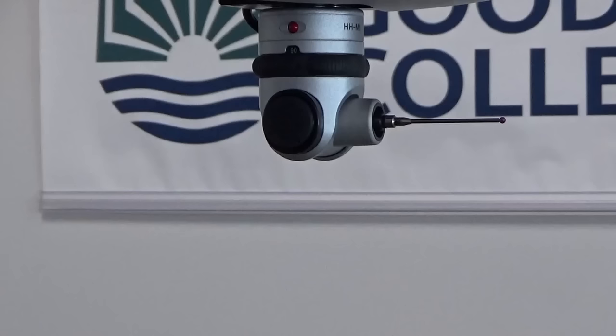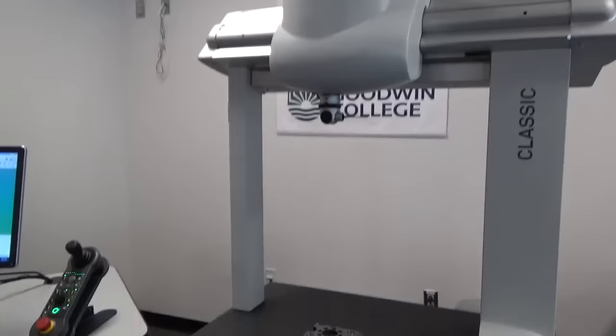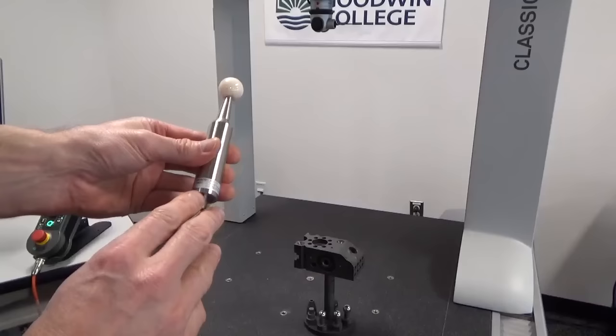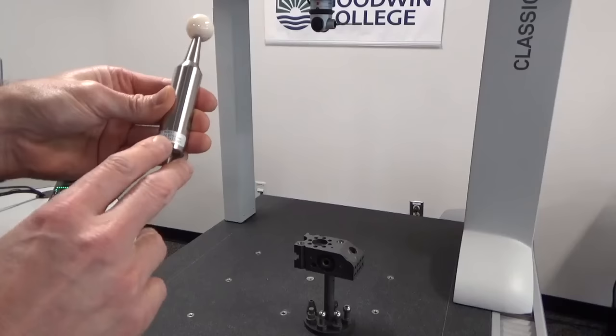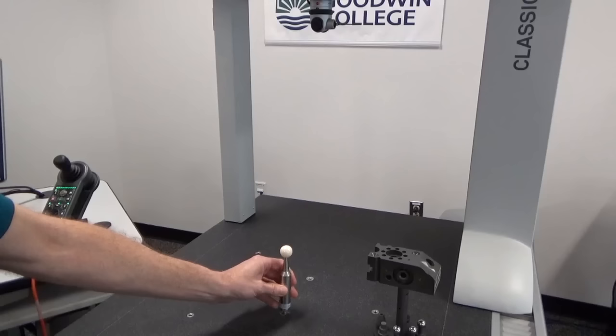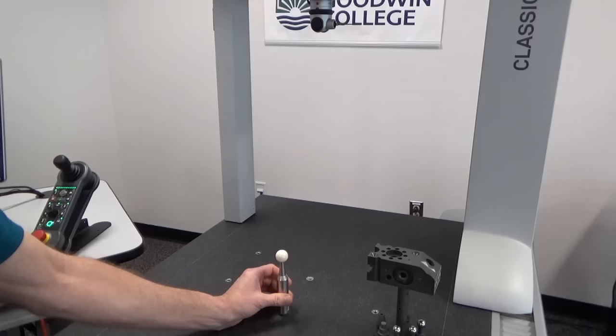So for every one of those positions that we have this we need to put a calibration in place for this probe. So the way this is done is we mount a special calibration sphere down onto the table. This is the calibration sphere, it comes with the instrument and on it it has information about how big the sphere is written right on its face and that's information that needs to go into the software.